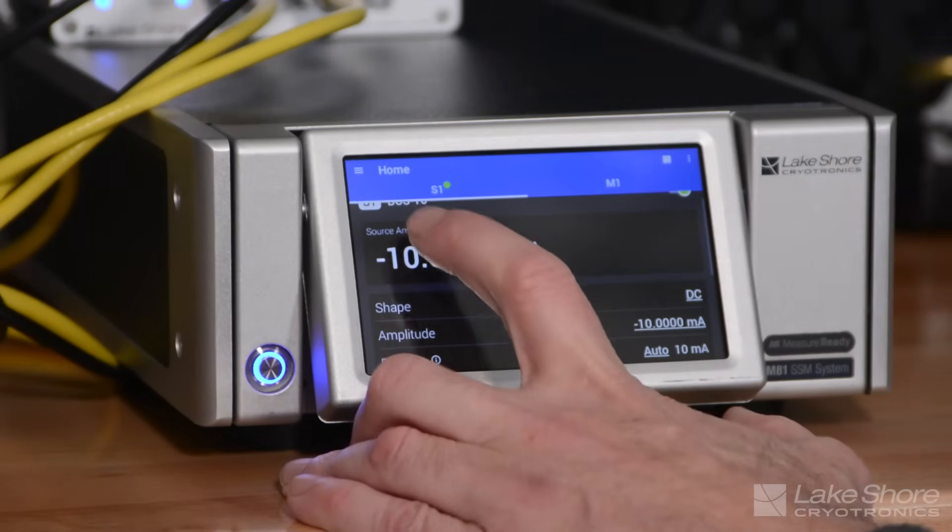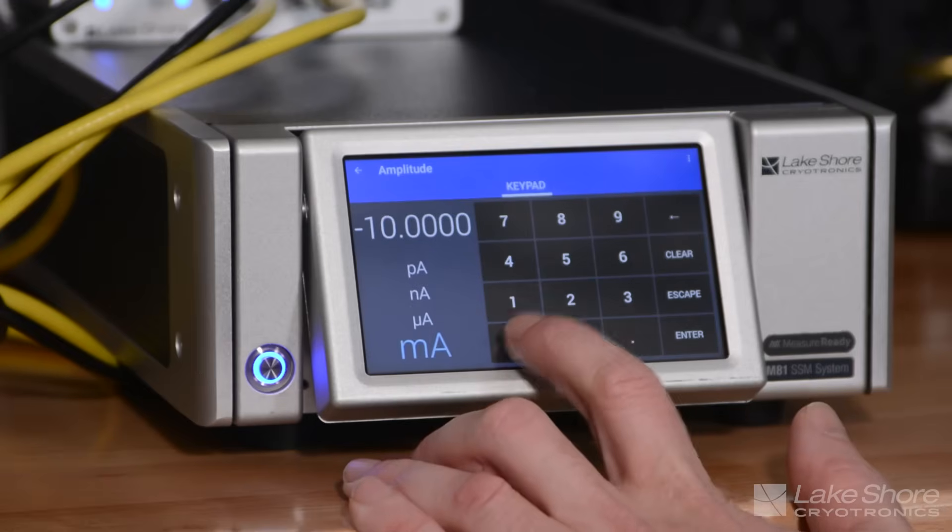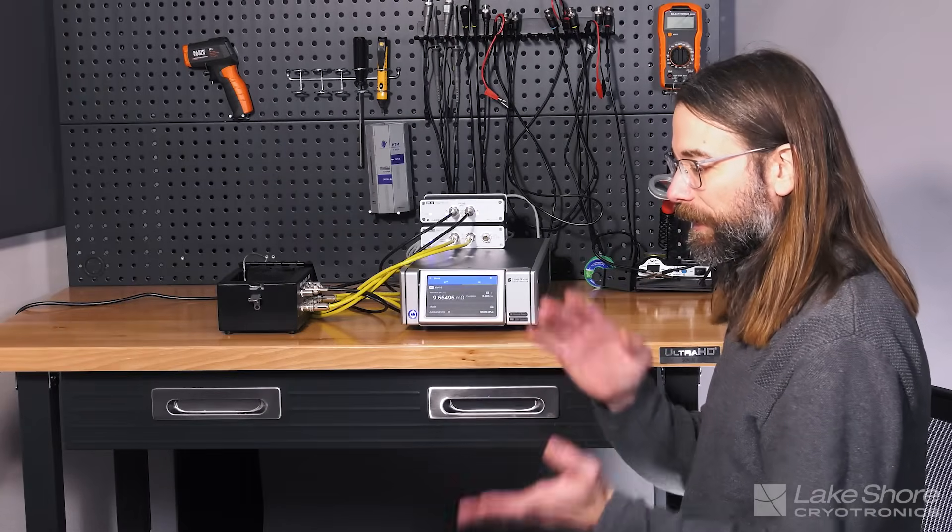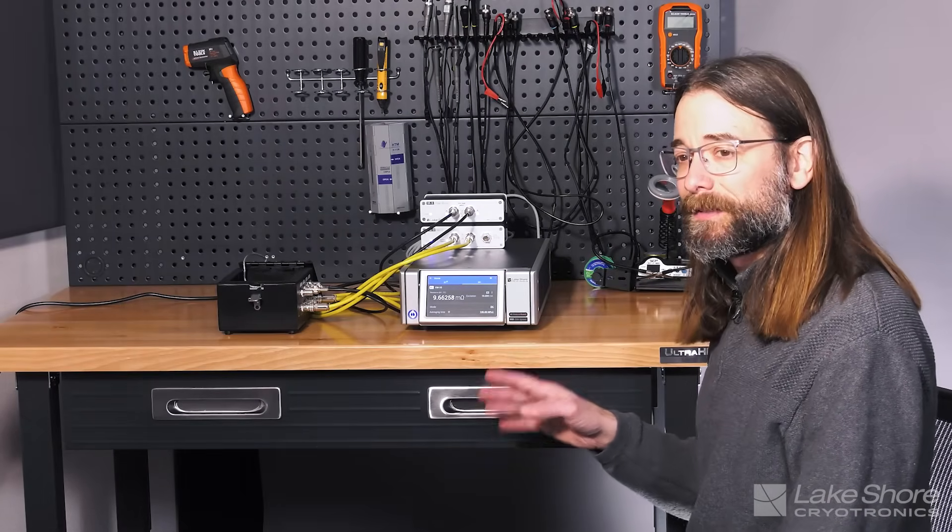So in this case, we're making a DC measurement on this device. So now we're reading 10.3 milliohms. And remember, in the positive direction, we were reading 9.6. And so I'm just going to switch back to the positive direction. 9.6. So we do have a discrepancy in the positive and the negative direction when we're sourcing a DC current.